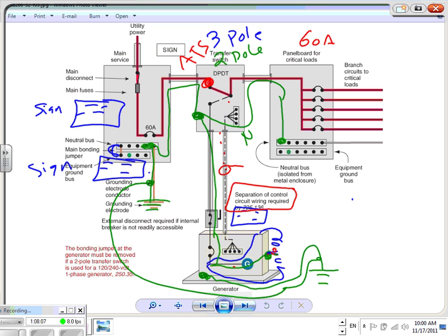I can't emphasize this enough, guys: when you study it, look how we separated the neutral. No more bonding. We do not bond here. Why? Because we're already bonded here if it's a non-separately derived system. And if it's a separately derived system, Chad, we're already bonded right in here, right at the generator. Any question?